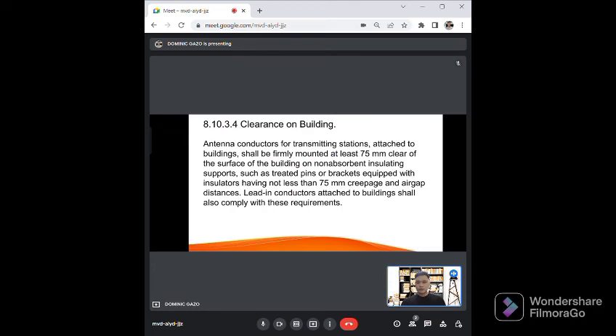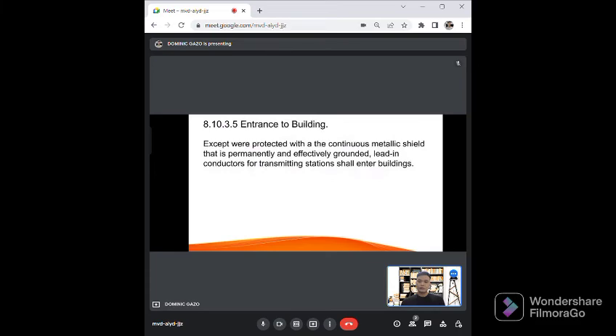8.10.3.4, the antenna conductors for transmitting stations that are attached to the buildings shall be firmly mounted at least 75 mm clear of the surface of the building, on non-absorbing insulating supports such as treated pins or brackets, with insulations having not less than 75 mm. For entrance of the buildings, except where protected with a continuous metallic shield that is permanently and effectively grounded, lead-in conductors for transmitting stations shall enter buildings.